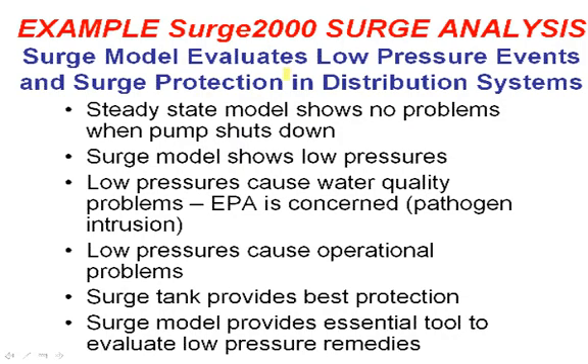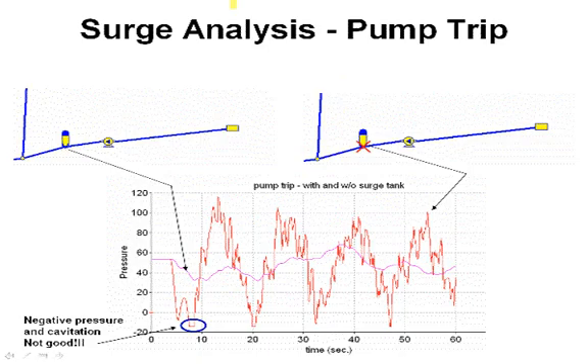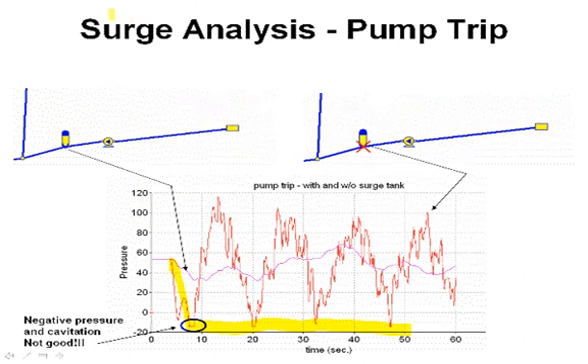A surge analysis: we saw earlier that if we shut the pumps off, the system behaves very well. But what happens if the pump trips — it loses power and you get a very fast shutdown? You can analyze this with no surge tank, which is the way the system would be. You get significant pressure variations and negative pressures, which is a very bad situation for water utilities. Negative pressures break seals and cause dirty water intrusion into the system.